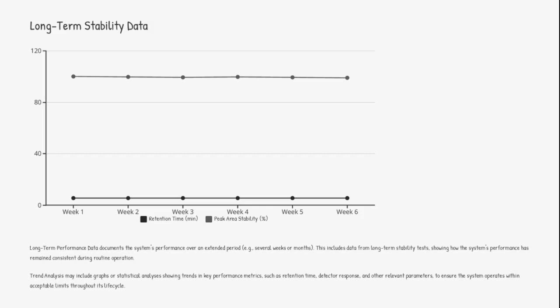Long-term stability data is essential for monitoring the system's performance over extended periods. This data includes retention time and peak area stability, ensuring the system remains consistent during routine operation. Trend analysis helps identify any deviations and ensures the system operates within acceptable limits.